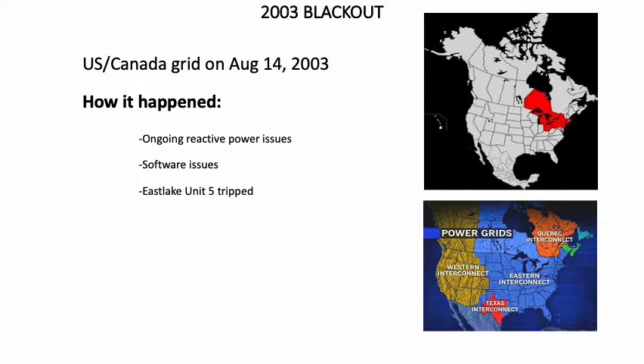The first outage was in East Lake Unit 5. East Lake Unit 5 is in northern Ohio, which had been running under stressed reactive power conditions. And as I said before, reactive power imbalances affect the voltage. So in turn, this caused the voltage regulator to trip on overexcitation. While the operator tried to restore the voltage regulator, the unit ended up tripping, and cascading events followed, leading to a severe blackout.